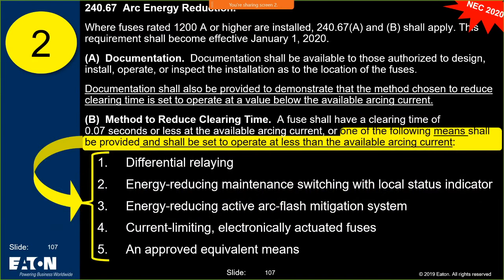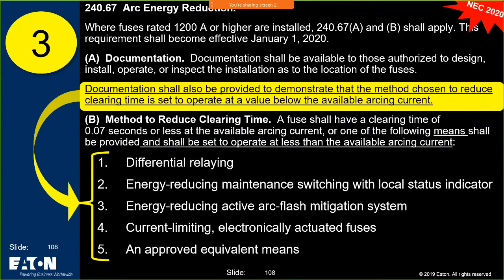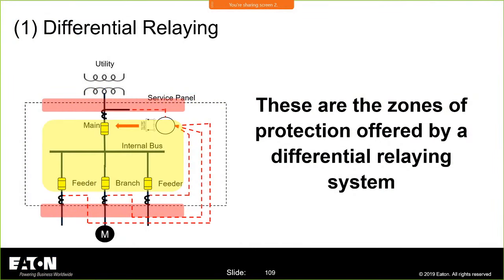All right, so now we're into what are the approved methods. If you need to put in an arc reduction technology, the methods for 240.67 are differential relaying, energy reduction maintenance switch, and energy reducing active arc flash mitigation system. So let's talk about the zones of protection. We had this on one of our quizzes. The way differential relaying works, the gazintas need to equal the gazaltas, okay? So whatever current goes into this zone has to come out of the zone.